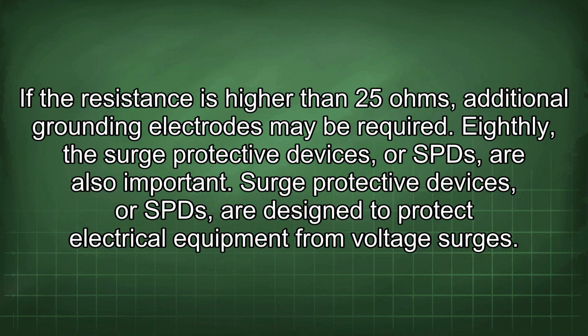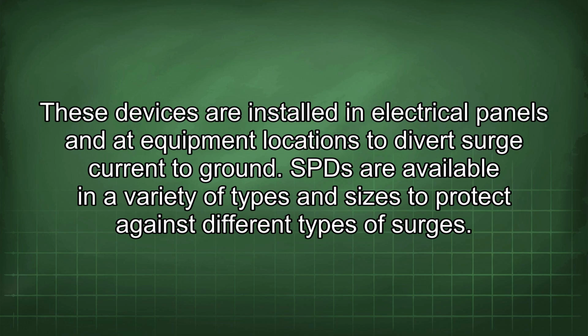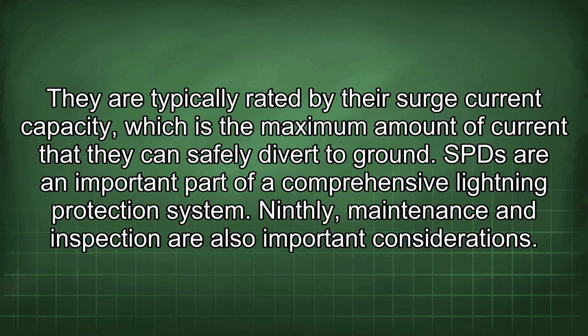Eighthly, the surge protective devices, or SPDs, are also important. Surge protective devices are designed to protect electrical equipment from voltage surges. These devices are installed in electrical panels and at equipment locations to divert surge current to ground. SPDs are available in a variety of types and sizes to protect against different types of surges. They are typically rated by the surge current capacity, which is the maximum amount of current that they can safely divert to ground. SPDs are an important part of a comprehensive lightning protection system.